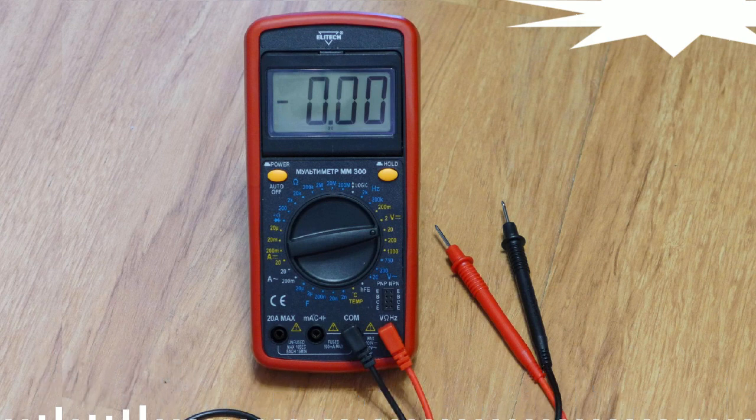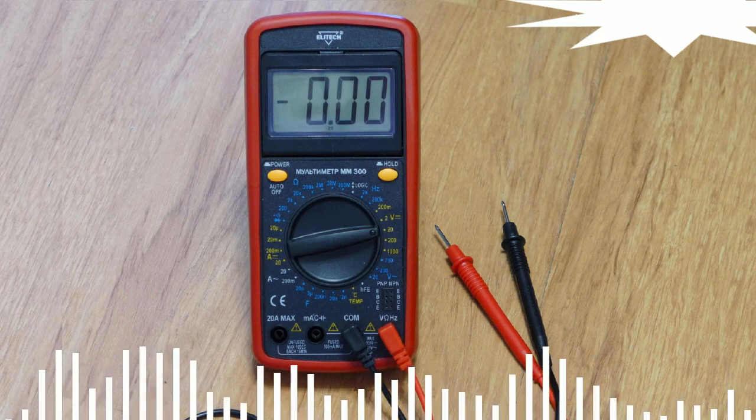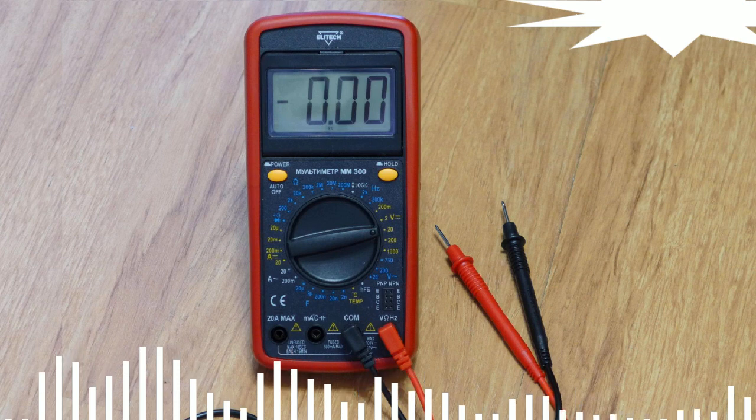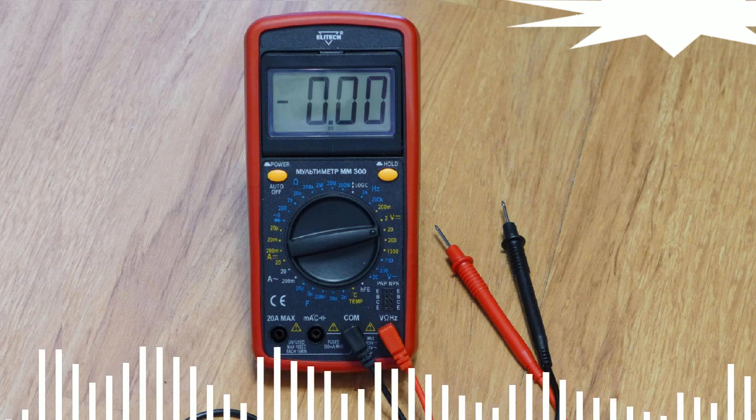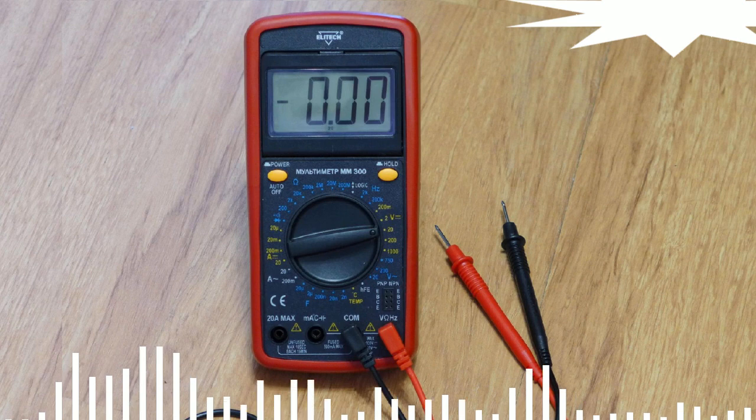Step 3. Measure indirectly. Connect a multimeter to the prepared open circuit of the electrical circuit and put the device into the current measurement mode. Turn on the voltage supply device input breaker or circuit breaker. Fix the data displayed on the indicator of the device. Disconnect the circuit voltage. Disconnect the multimeter from the circuit and restore the circuit as it was before the measurements.